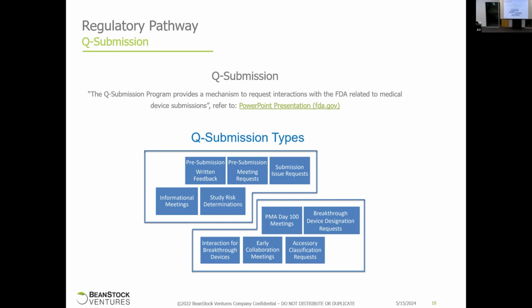Pre-sub. So pre-sub is a meeting with the FDA before you actually do your submission, or if you're looking for breakthrough or de novo designation. So this is a free meeting with the FDA. There's some guidance here on how to actually conduct the meeting, but it's really helpful for submissions that are PMAs. That's very important. If you're de novo, that's also very important.